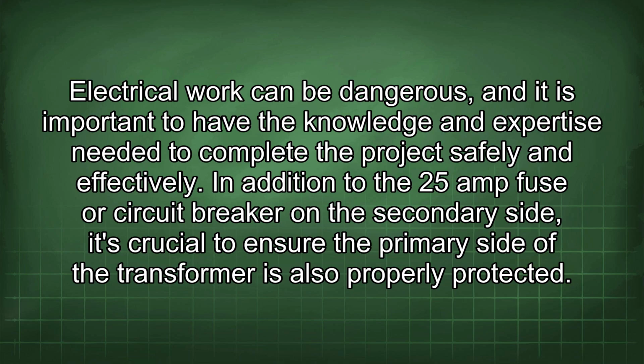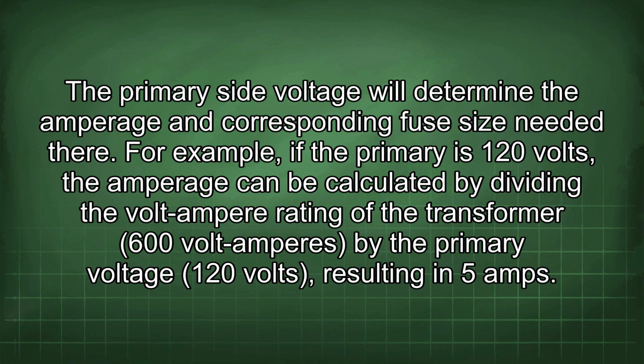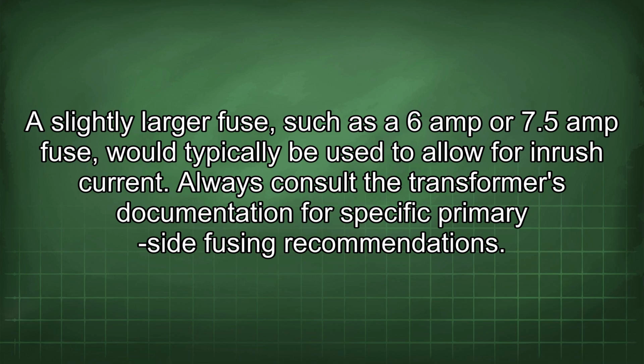ensure the primary side of the transformer is also properly protected. The primary side voltage will determine the amperage and corresponding fuse size needed there. For example, if the primary is 120 volts, the amperage can be calculated by dividing the volt-ampere rating of the transformer, 600 volt-amperes, by the primary voltage, 120 volts, resulting in 5 amps. A slightly larger fuse, such as a 6 amp or 7.5 amp fuse, would typically be used to allow for inrush current. Always consult the transformer's documentation for specific primary side fusing recommendations.